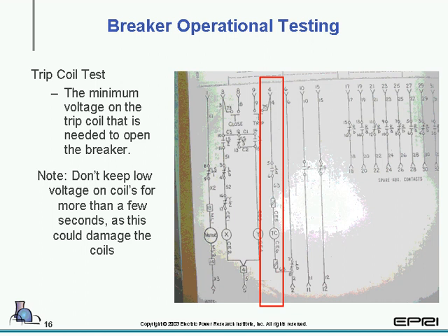Breaker trip coil testing. Now, again, we want to check the minimum voltage on the trip coil that is needed to open the breaker. What we're trying to say here is, with the close coil, we set it up so it closed at 70% of its nominal voltage.